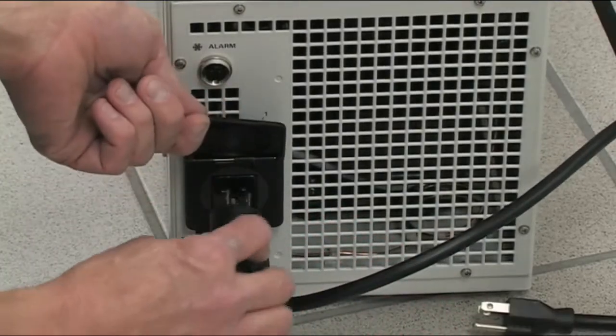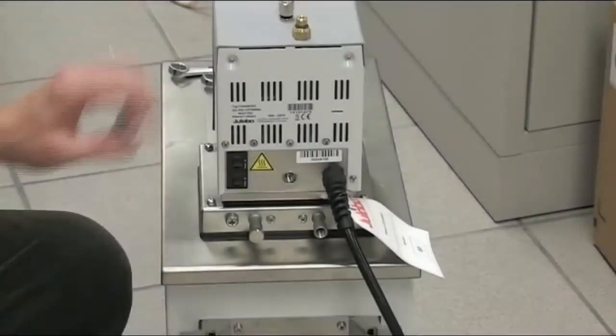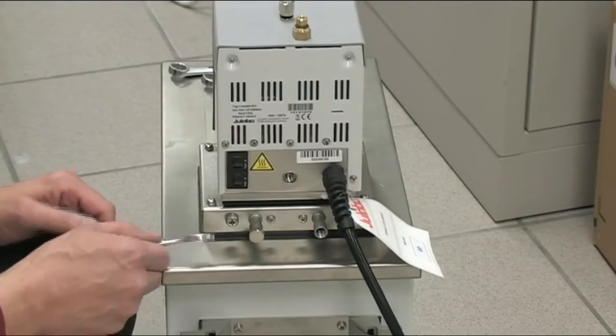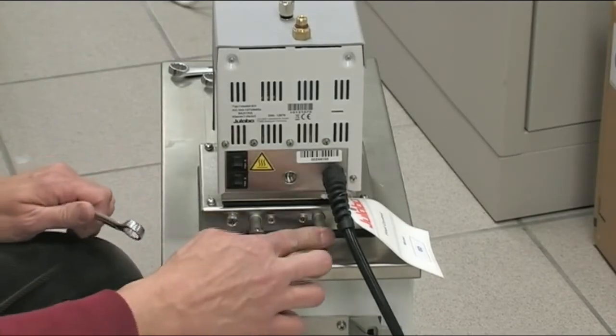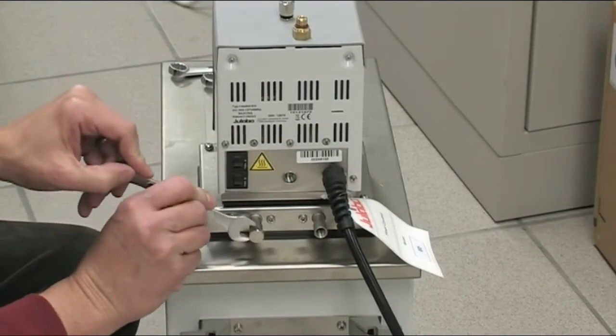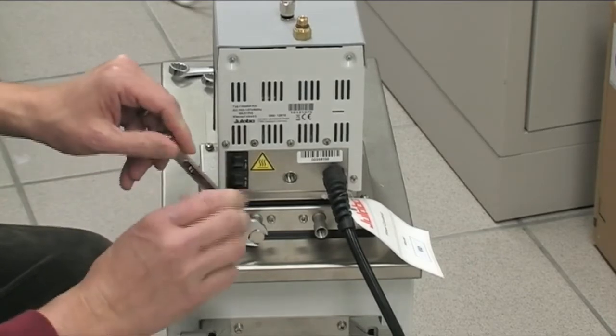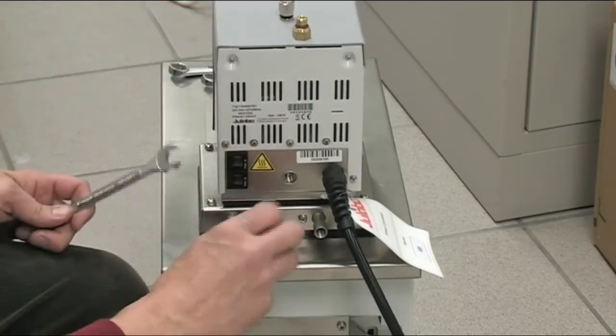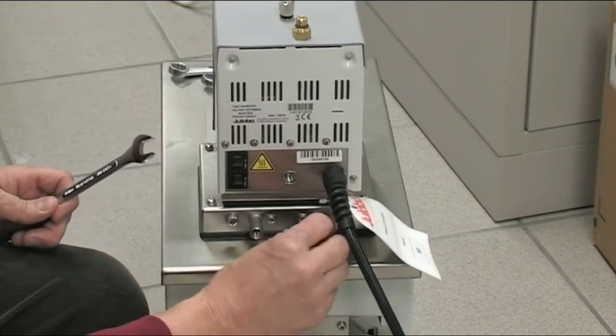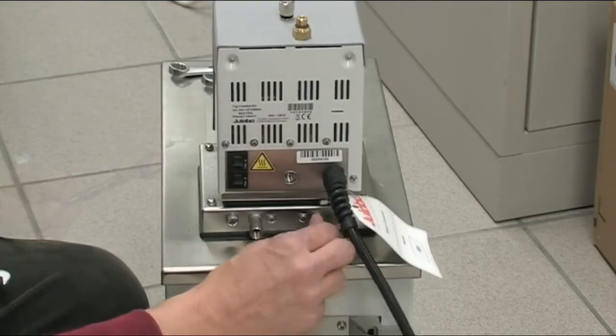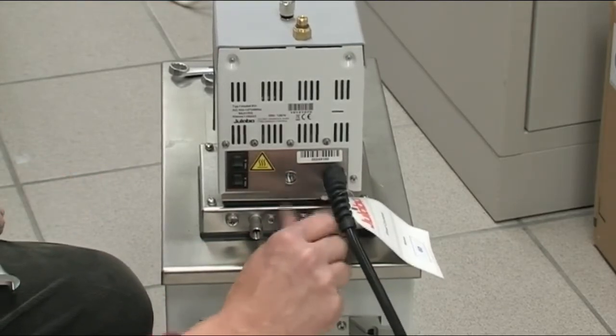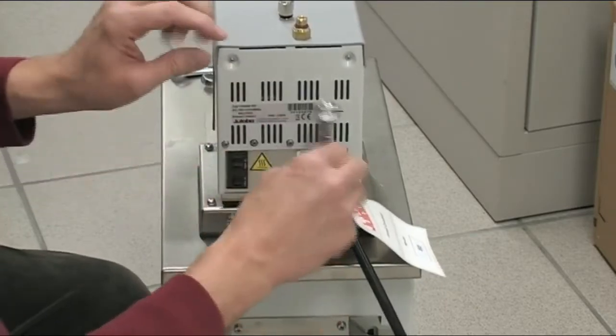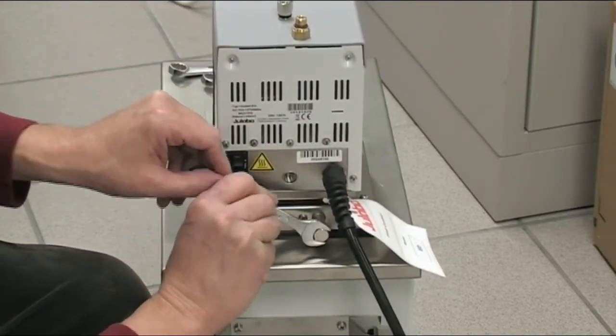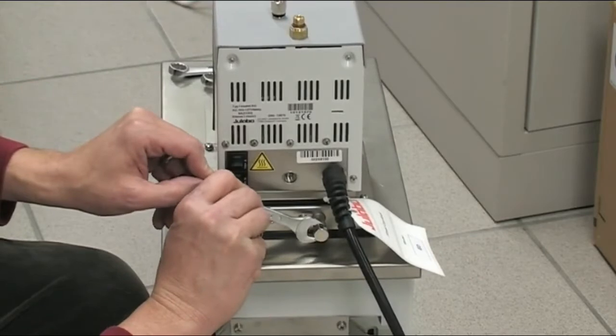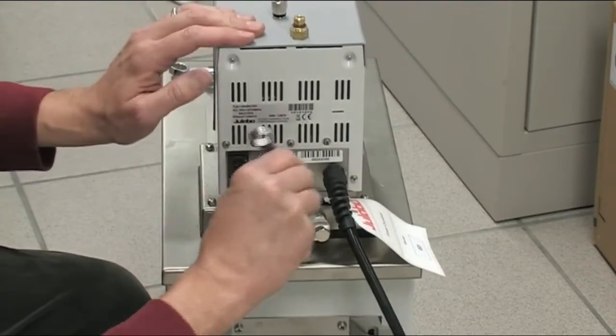You then want to plug the pump into the condenser unit. The next thing you have to make sure is the plug is located correctly. The plug goes on the right side of the instrument. So what you have to do is take the plug out, and it uses, unfortunately, a metric wrench, 13 millimeter. You want to remove this and place it in the right side.